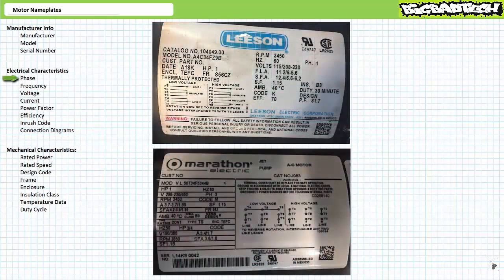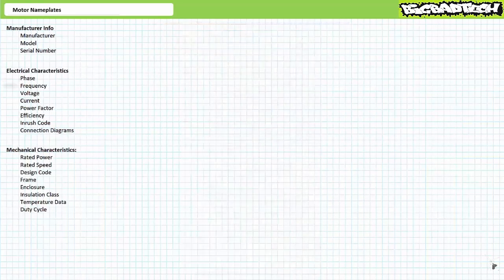Phase. The phase entry specifies if the motor in question is intended for use in an industrial 3-phase AC environment or a residential single-phase AC system. Compare and contrast these two 1 horsepower motor nameplates. Even though these are both 1 horsepower motors that run at the same speed, they are not equally applicable because this 1 horsepower motor necessitates 3-phase AC, whereas this 1 horsepower motor necessitates single-phase AC.